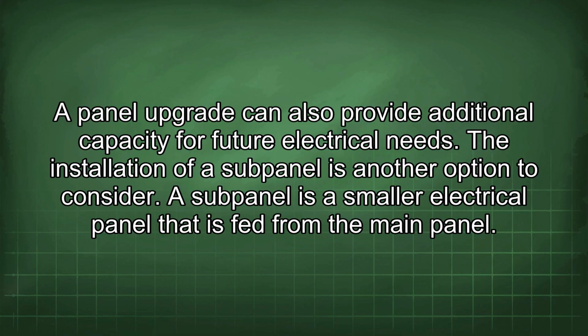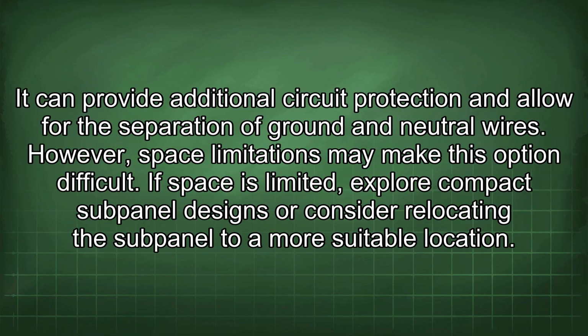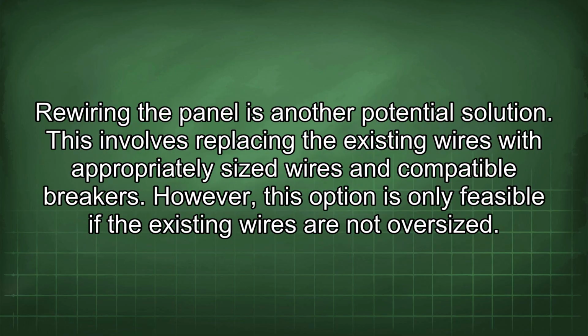The installation of a subpanel is another option to consider. A subpanel is a smaller electrical panel that is fed from the main panel. It can provide additional circuit protection and allow for the separation of ground and neutral wires. However, space limitations may make this option difficult. If space is limited, explore compact subpanel designs or consider relocating the subpanel to a more suitable location. Rewiring the panel is another potential solution.